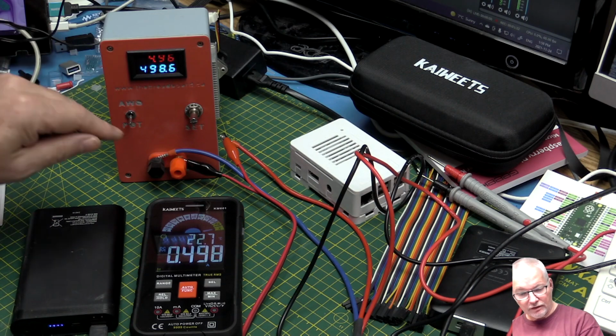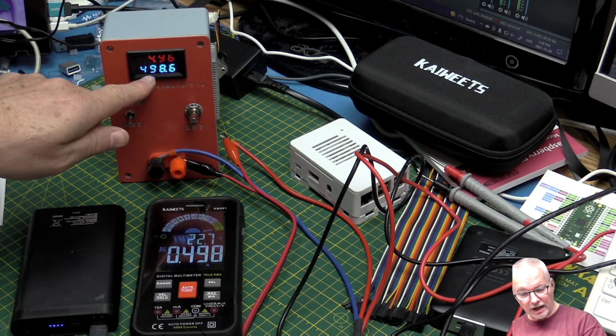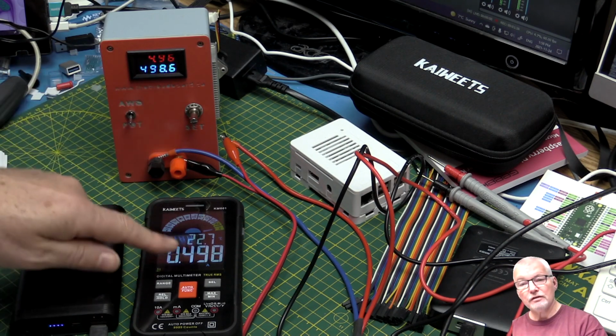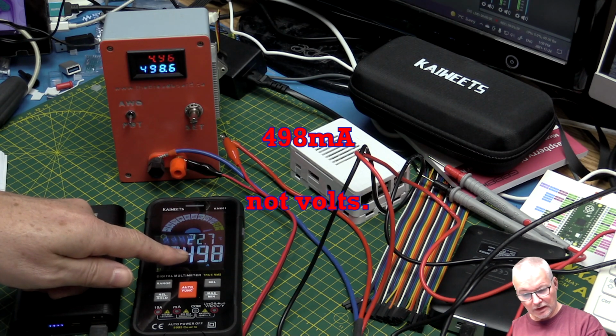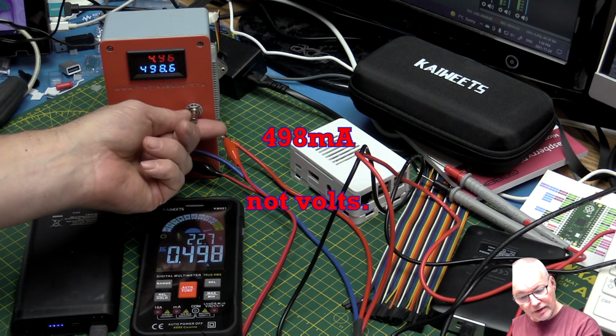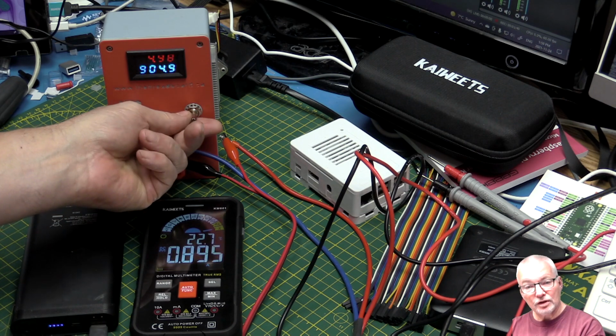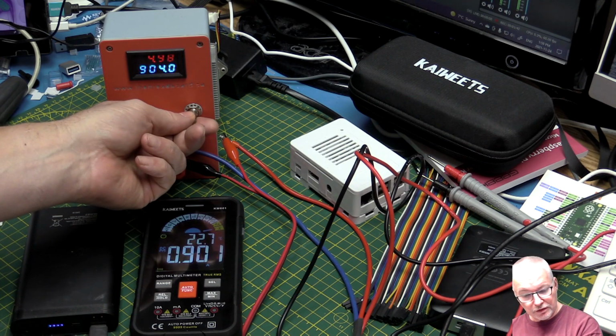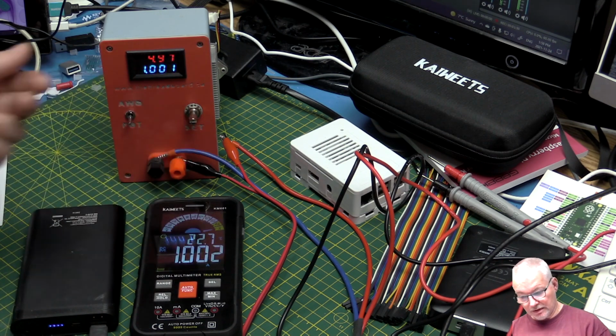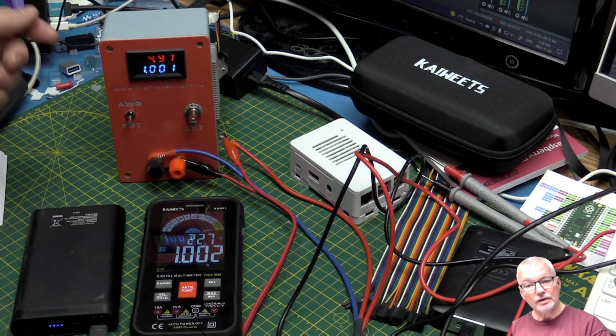I've got it set to 498 milliamps, and we're reading 498 down here on the current range. Let's crank it up to an amp to make sure I'm on the right input. If I was on the milliamp input, I would have blown the fuse by now. There's 1 amp, and we're reading nicely 1 amp.